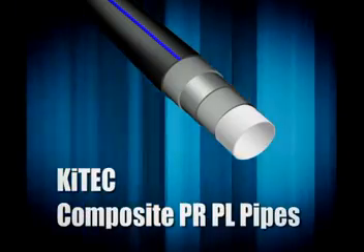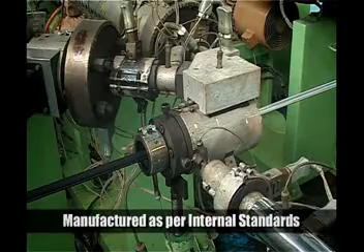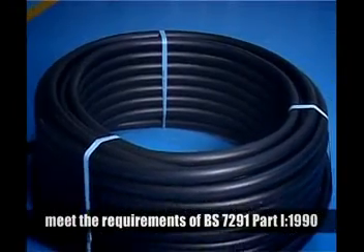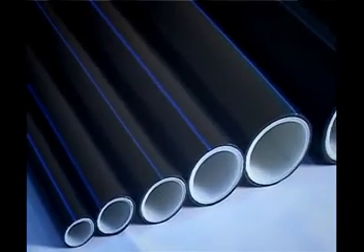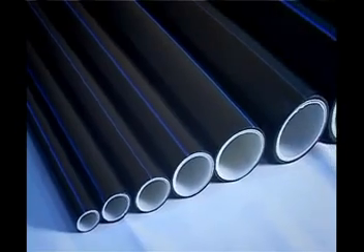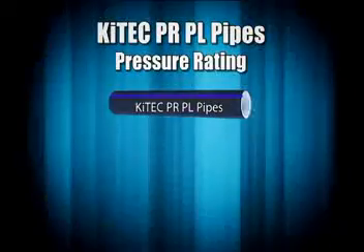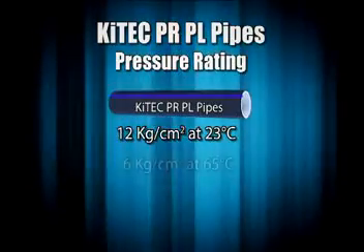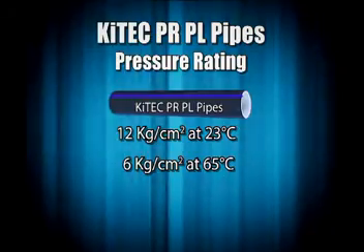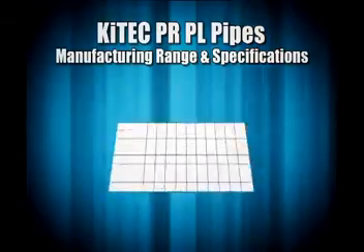KiTEC composite PR-PL pipes. KiTEC composite PR-PL pipes are manufactured as per internal standards and meet the requirements of BS 7291, Part 1 1990, the specifications for thermoplastic pipes and associated fittings for hot and cold water for domestic purposes and heating installations. KiTEC composite PR-PL pipes have a pressure rating of 12 kg per centimeter square at 23 degrees Celsius and 6 kg per centimeter square at 65 degrees Celsius. The manufacturing range and specifications are as follows.